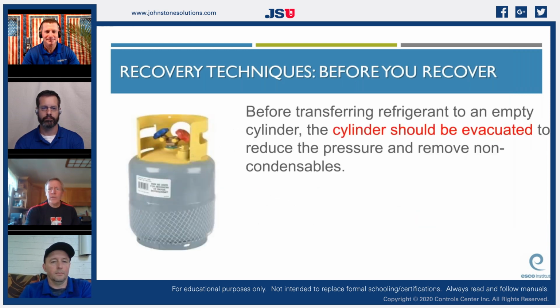We did this as well, and I think Brian mentioned this yesterday. I know Clifton did in the core. Your cylinders should be evacuated. All the cylinders we have at our shop that we sell are in a vacuum. But with the techs in the field, we would bring them in and recover them into a large cylinder, I think a 500-pound or 1,000-pound cylinder. Then we'd put a vacuum pump on our recovery tank and actually pull a vacuum on them.